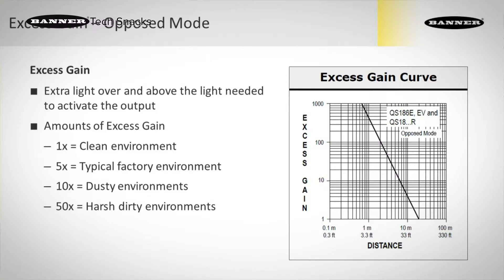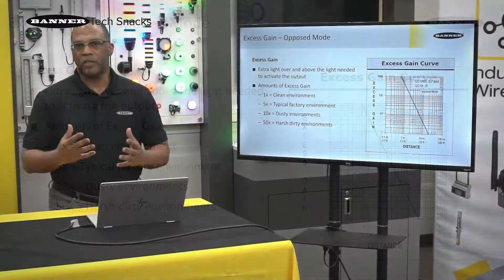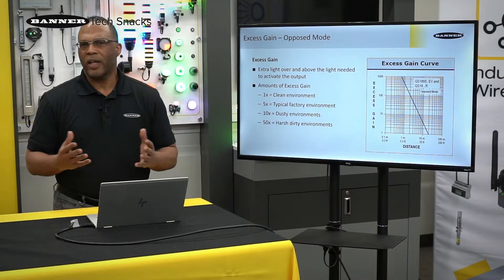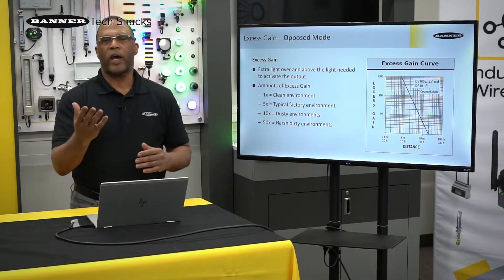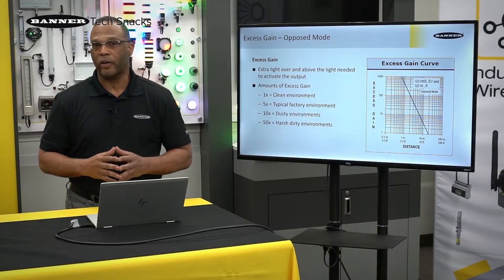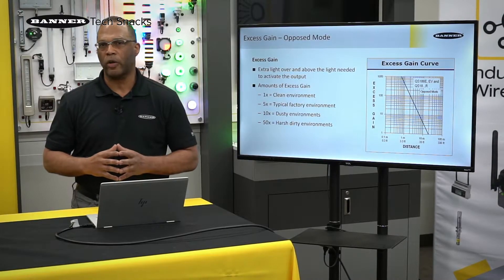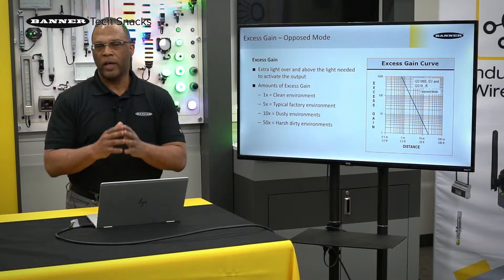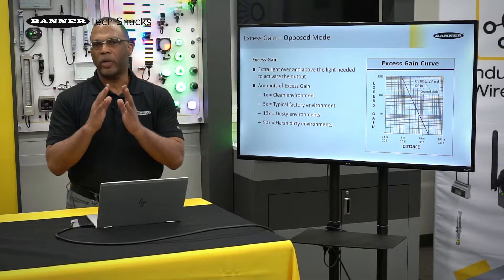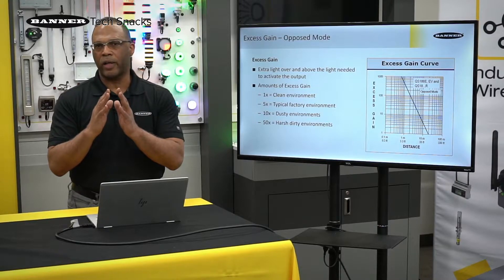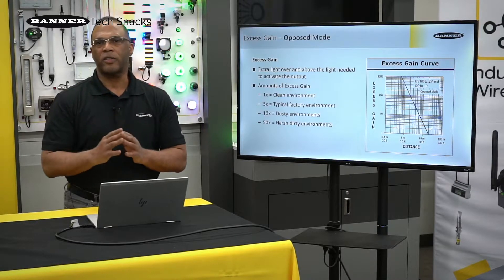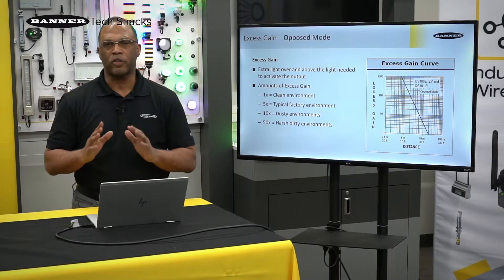So in this chart that we're looking at, out at 20 meters we have an excess gain of one. Now that means the sensor can see a target, but barely. That's equivalent to you and I going to the eye doctor and they say, 'What's the smallest chart you can read?' You may be able to read that chart, but just barely.